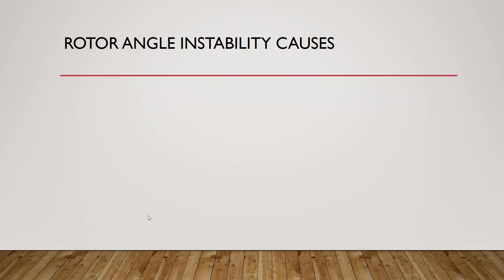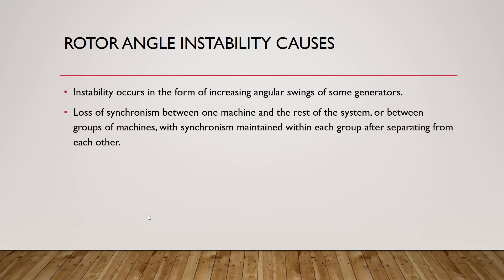When rotor angle is unstable, several consequences occur. First, it manifests as increasing angular swings of some generators, with delta increasing to infinity theoretically. Second, there is a loss of synchronism between one machine and the entire power system, or between groups of machines that are synchronized with each other but not with the rest of the power system. Additionally, rotor angle instability can cause tripping of generators, leading to loss of generation and a drop in bus voltages.